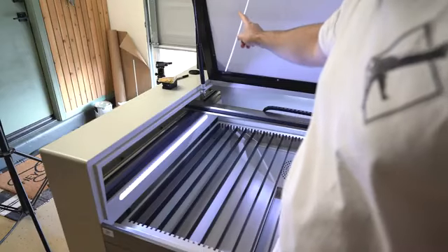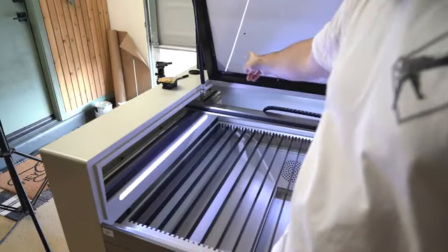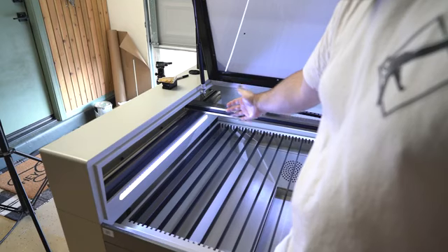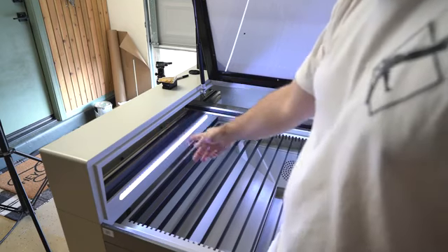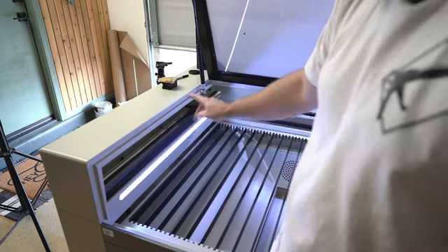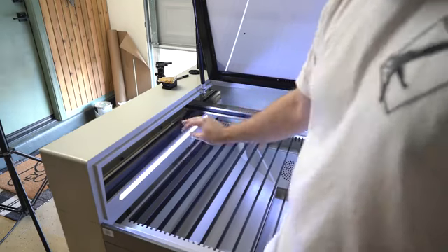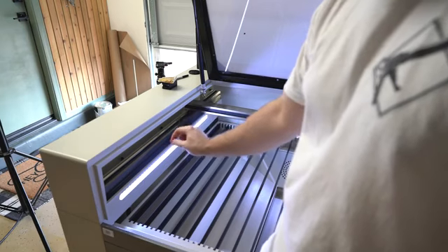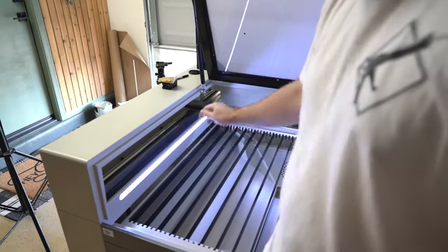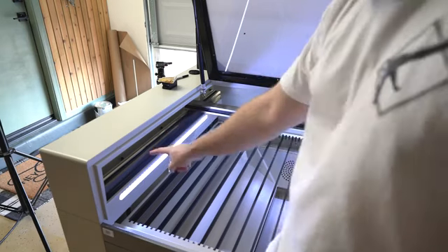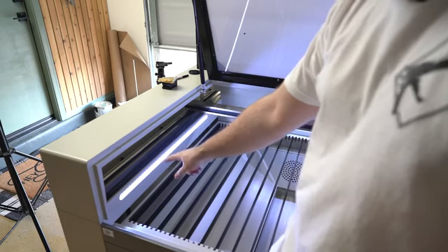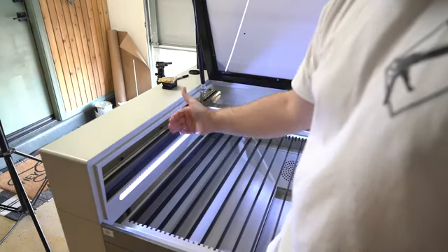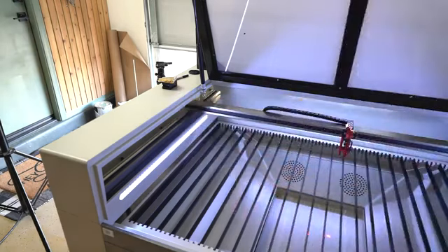With the back mirror aligned with the gantry close to that mirror, let's move the gantry far away and double check to make sure at a far distance it's also aligned. If it's unaligned, this is definitely going to be much more micro adjustments, because the distance from that back mirror to this mirror housing when it's all the way up here in the front is going to cause much more movement of that laser beam. So let's move it up.